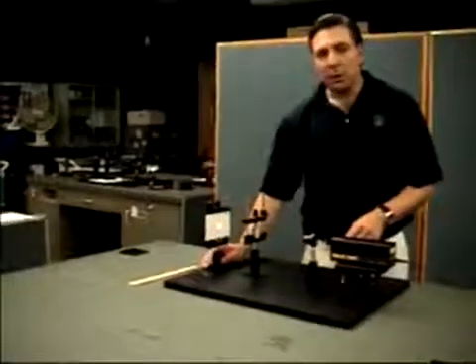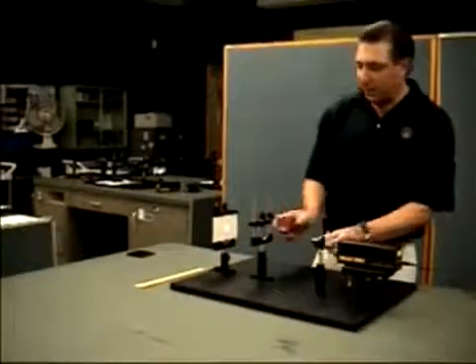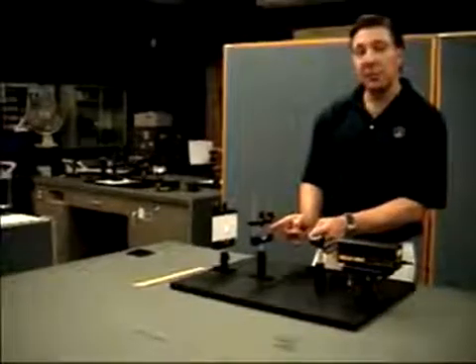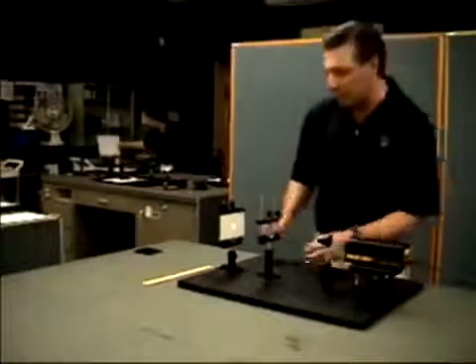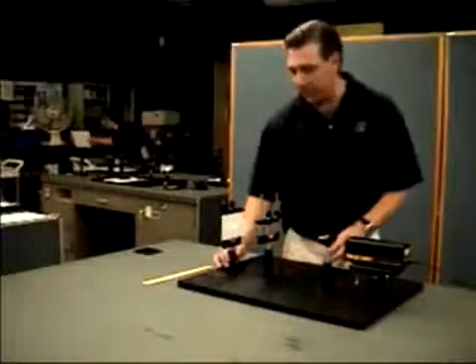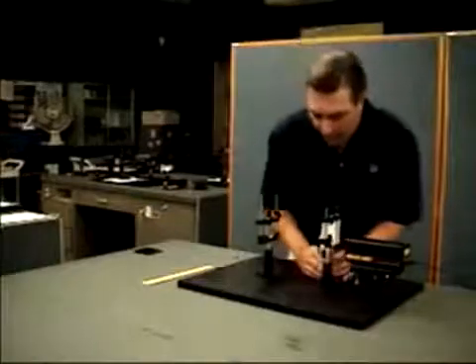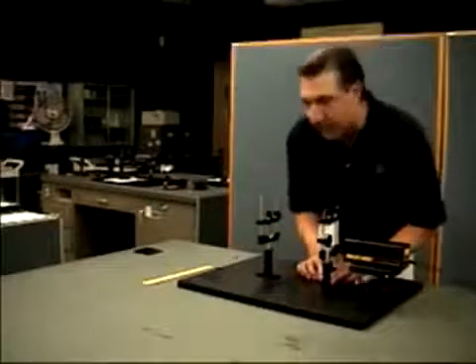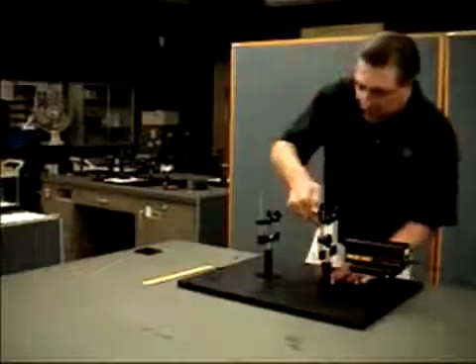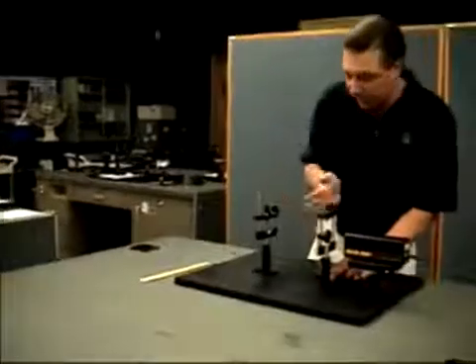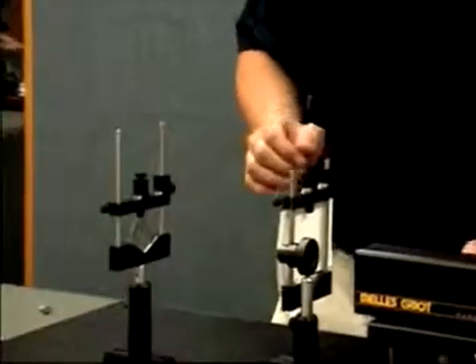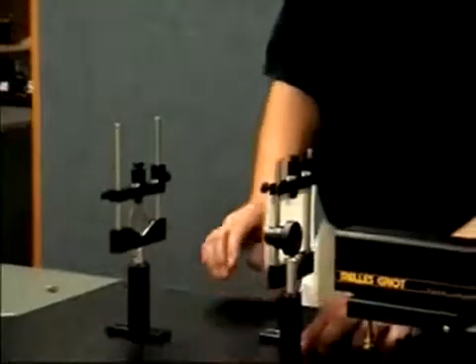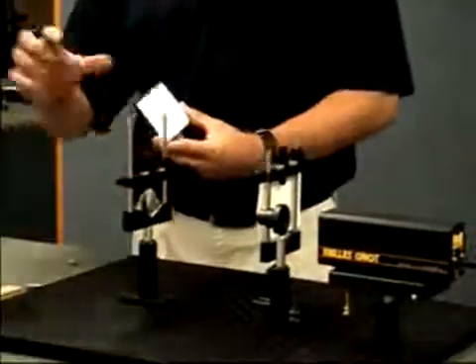What happens in autocollimation is that if the back focal length of the collimating lens coincides with the front focal point of the expanding lens, then that beam will be collimated. So what we're going to do to check that out is we're going to take our target and I'm going to position it about eight millimeters just off axis, about eight millimeters in front of the microscope objective. So this plane is co-aligned with the focal point of that lens. And what I'm going to use that for is to reflect the light back, which is the principle of autocollimation.